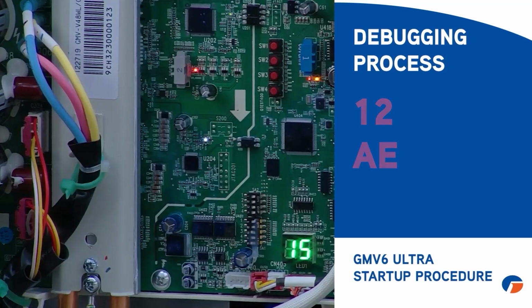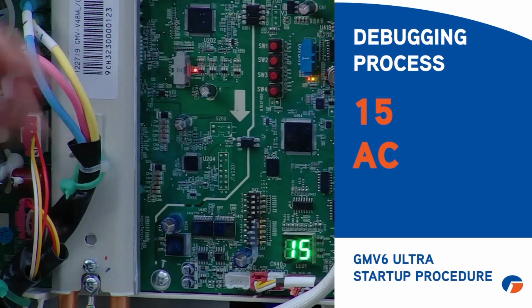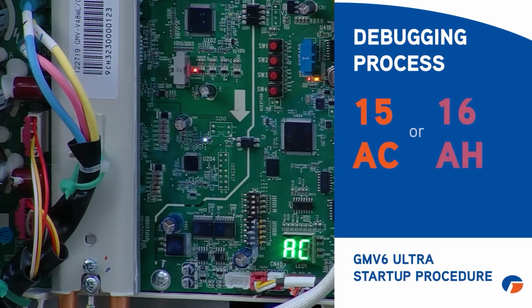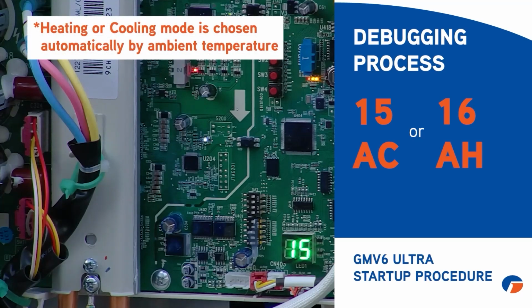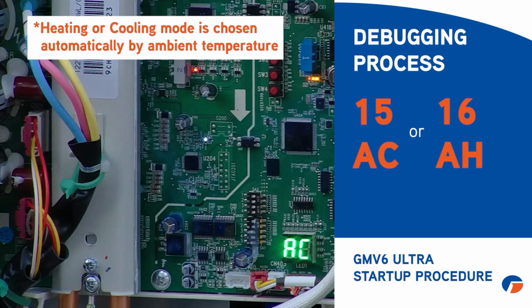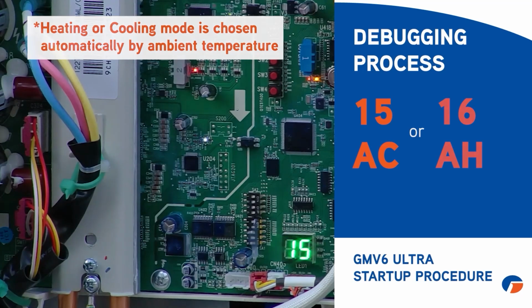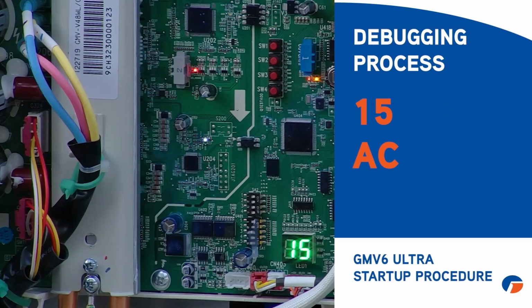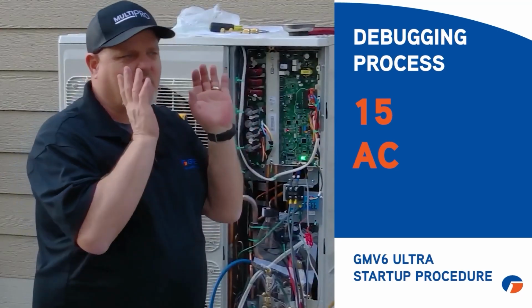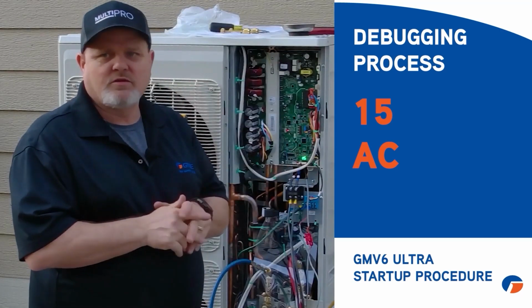So it's step 12 AE, 15 AC. When it hits 15 AC, it's either going to hit 15 AC or it's going to hit 16 AH. You have no choice. It does it by the ambient temperature. And what the machine's going to do now is start this thing up and run in cooling mode and do its whole debug process, and that takes about 50 minutes. I always tell guys on the phone, go get a donut and come back in about an hour, because right now you just need to let it do its thing. It'll run its whole debug process.